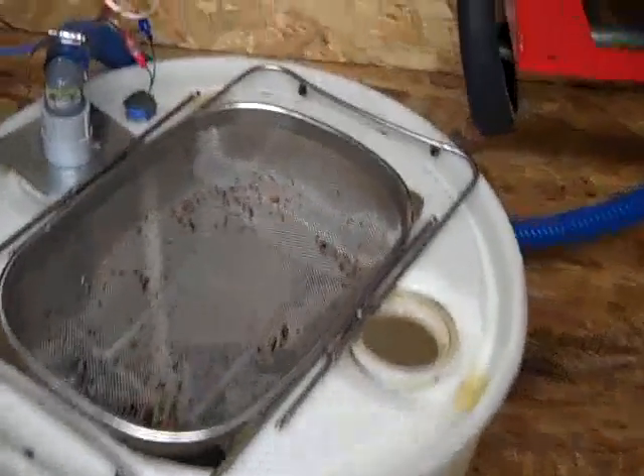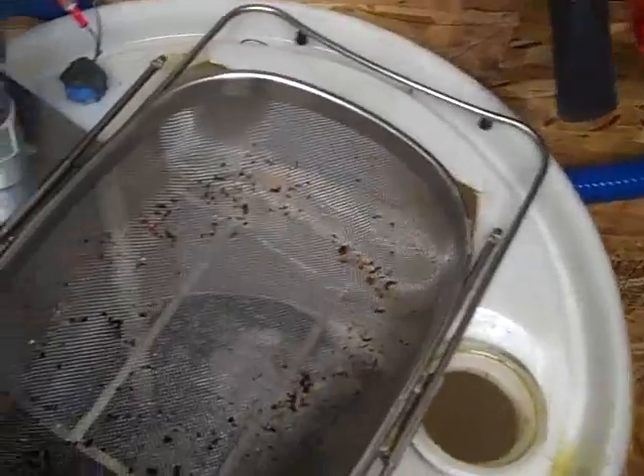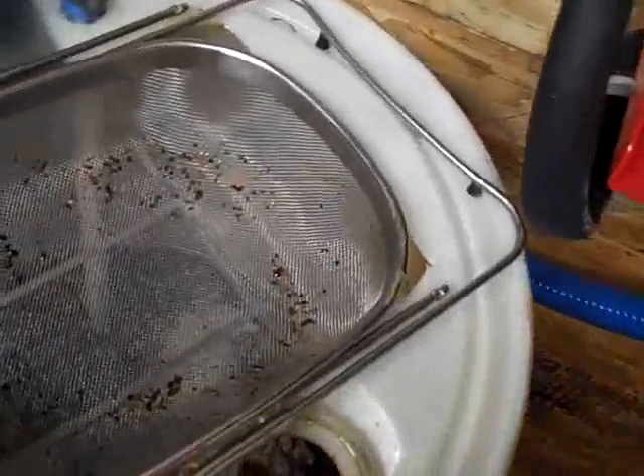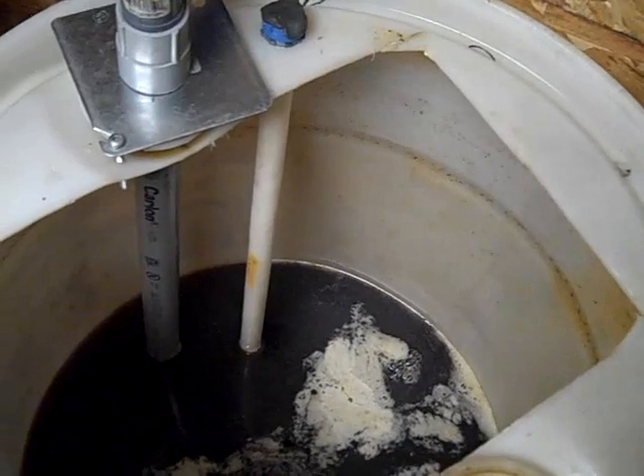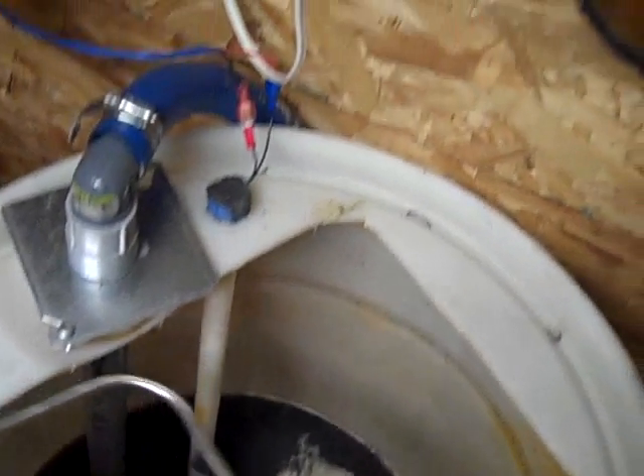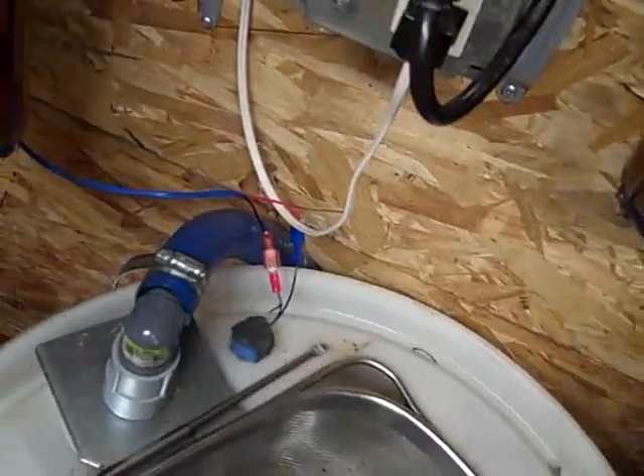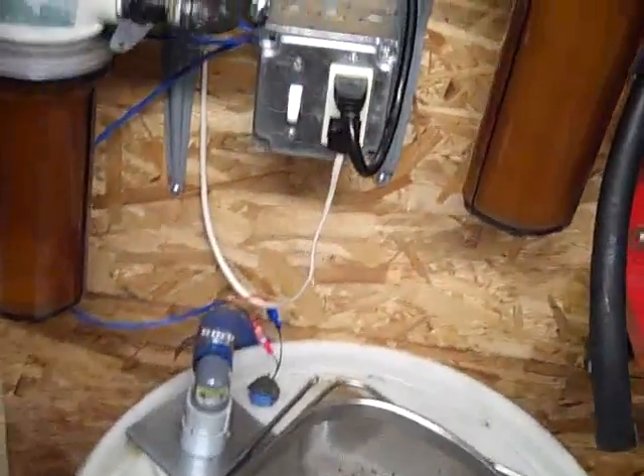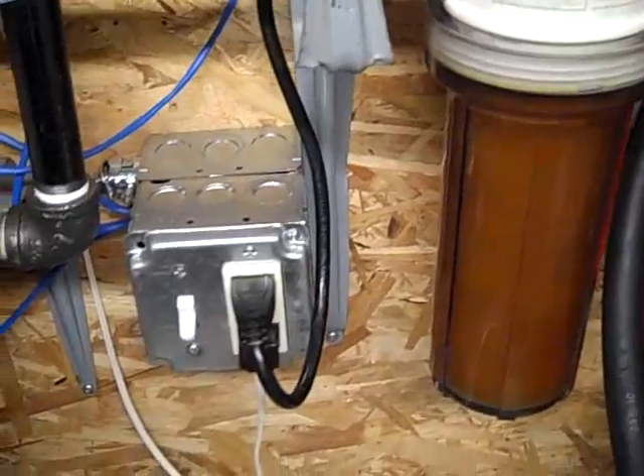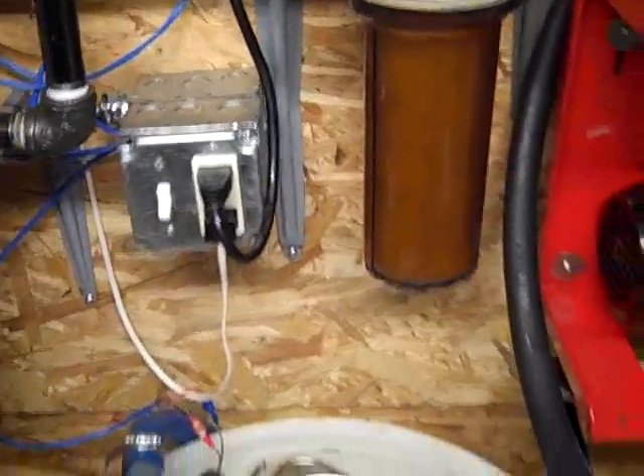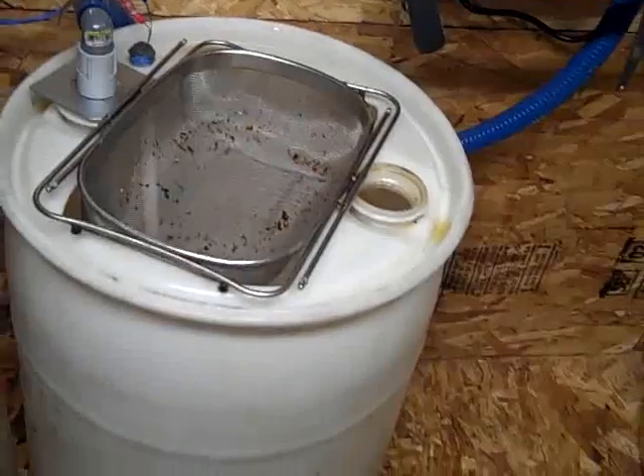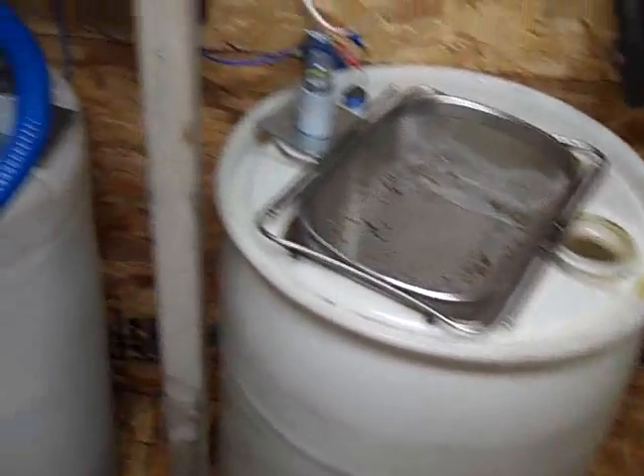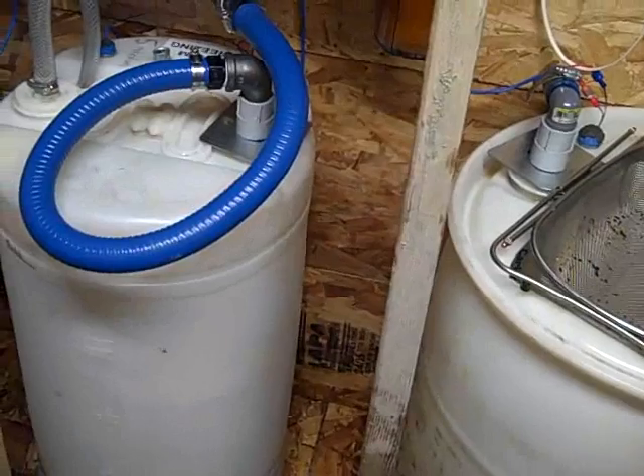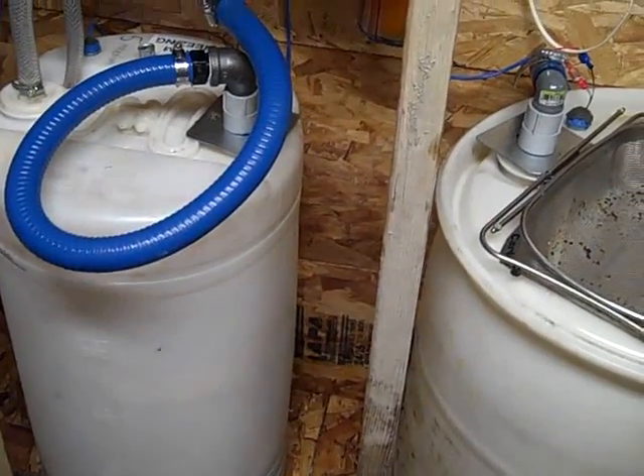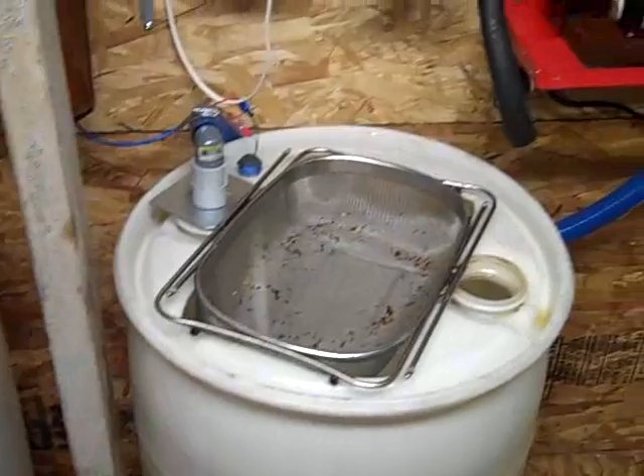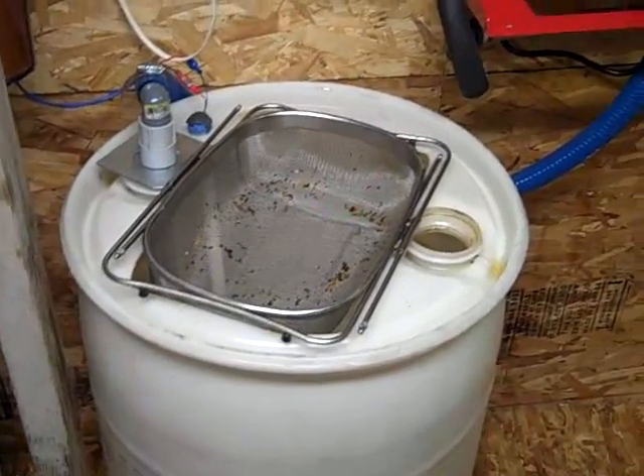Inside this barrel I have floats, which you can't see right here because it is below the oil level. On that white pipe there, we can see we have wires connected to it, and those wires come up into a contactor which will be in the outlet box here. I have a float here which will turn the pump on when there's oil in the barrel, and then I have a secondary float in here which will turn the pump off when this barrel becomes full, so that this pump is controlled by either an empty barrel or a full barrel.